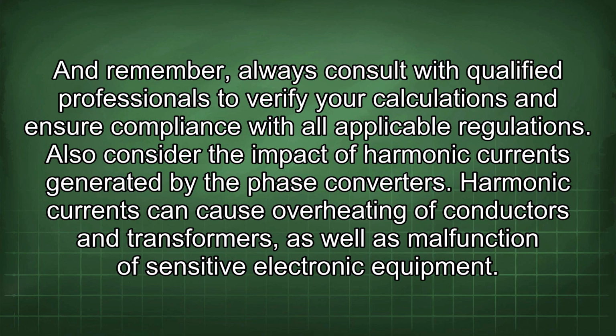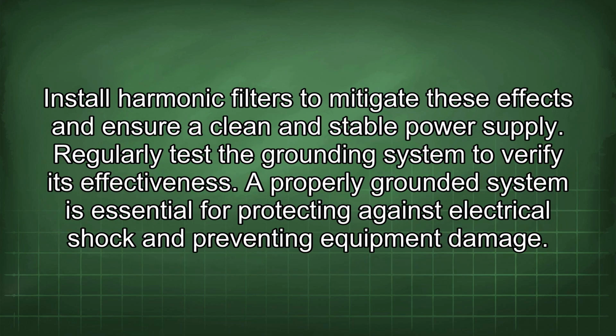Also consider the impact of harmonic currents generated by the phase converters. Harmonic currents can cause overheating of conductors and transformers, as well as malfunction of sensitive electronic equipment. Install harmonic filters to mitigate these effects and ensure a clean and stable power supply.